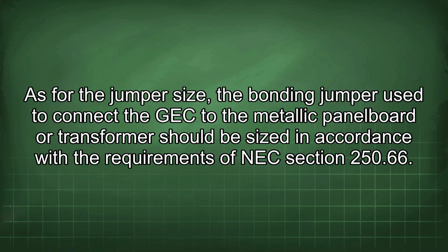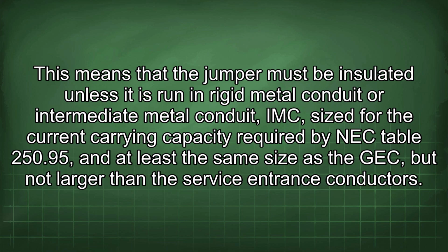As for the jumper size, the bonding jumper used to connect the GEC to the metallic panel board or transformer should be sized in accordance with the requirements of NEC section 250.66. This means that the jumper must be insulated unless it is run in rigid metal conduit or intermediate metal conduit, IMC, sized for the current carrying capacity required by NEC table 250.95, and at least the same size as the GEC, but not larger than the service entrance conductors.